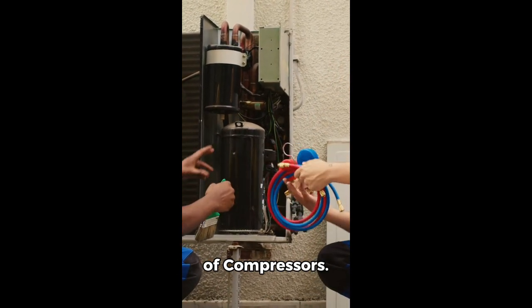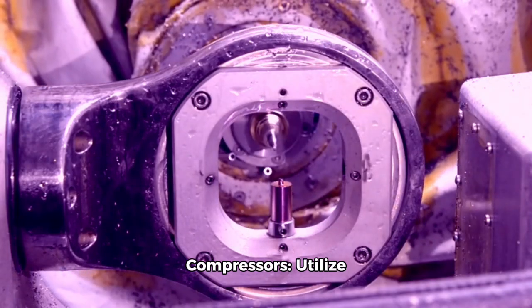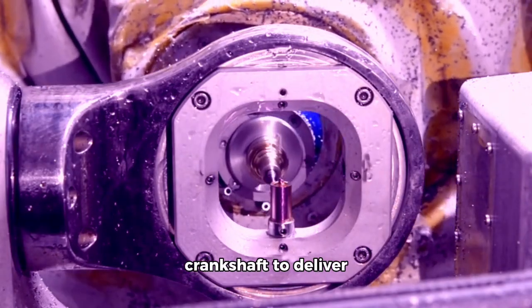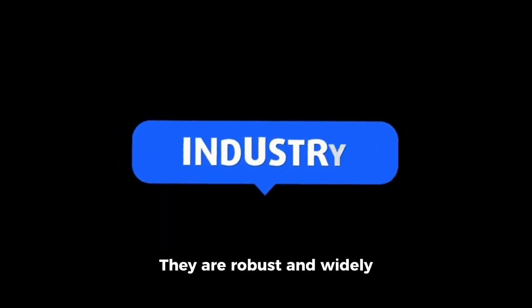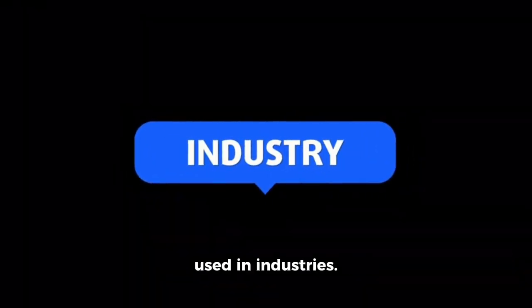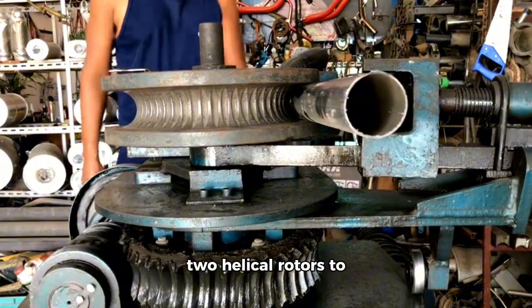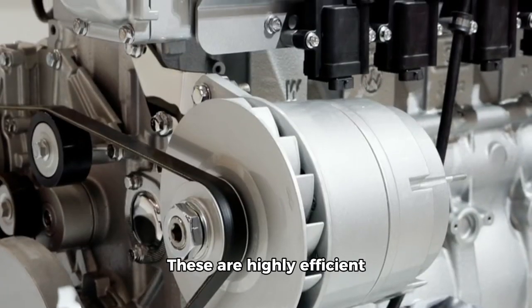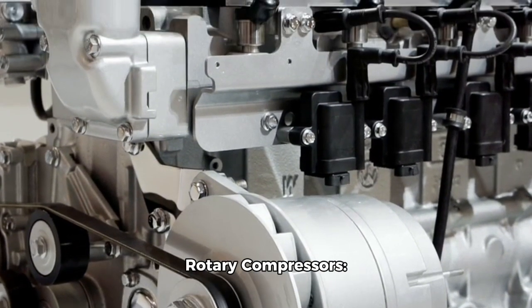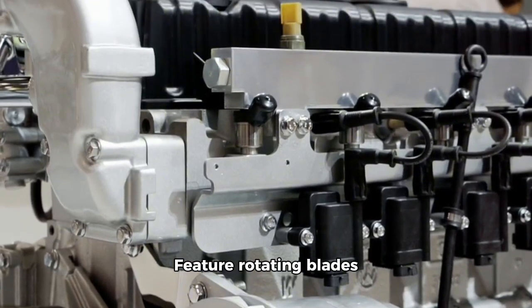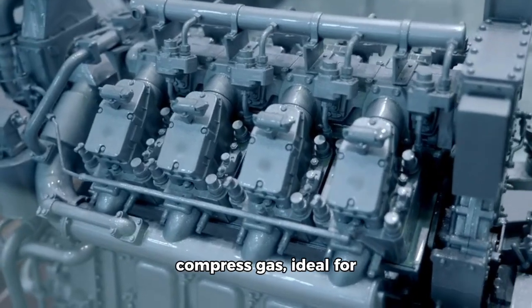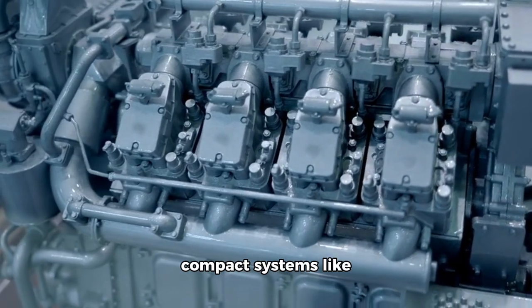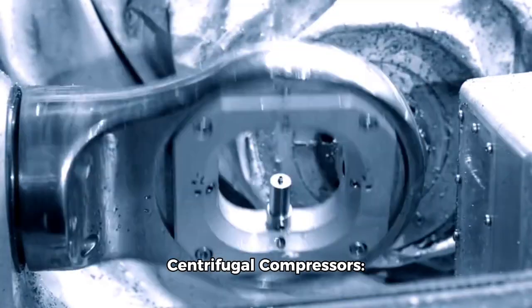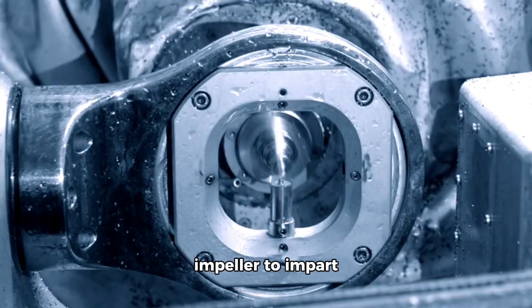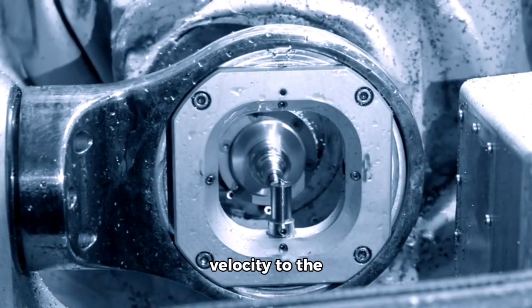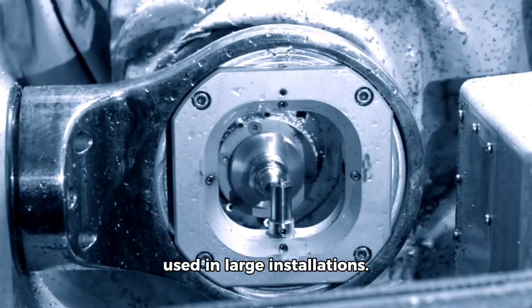Types of compressors. Reciprocating compressors utilize pistons driven by a crankshaft to deliver gases at high pressure. They are robust and widely used in industries. Screw compressors use helical rotors to compress the gas. These are highly efficient for continuous operations. Rotary compressors feature rotating blades within a cylinder to compress gas, ideal for compact systems like household refrigerators. Centrifugal compressors employ a high-speed impeller to impart velocity to the refrigerant, commonly used in large installations.